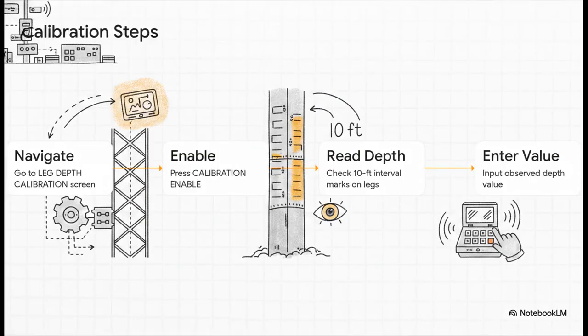So how does the system know where it is? Well, it relies on an incremental encoder on motor A1 on each leg to measure relative position, but it needs you to give it the absolute starting point. To set the absolute depth, you just follow this sequence. First, navigate to the calibration screen. Second, press Enable. And then, this is the really crucial physical part of the job, visually confirm the actual 10-foot weld marks painted and welded onto the legs themselves out on the deck. Do not guess here. Once you have eyes on that physical marking and you've confirmed the exact draft, you enter that observed value at the console. Boom! Now your digital control system is perfectly synchronized with reality.